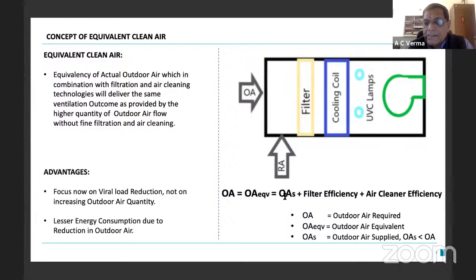This outdoor air equivalent now has three components: the minimum air required, then filter efficiency based on the filtration, and then the air cleaning capacity of the AHU. These three components will now provide the same equivalent of outdoor air which we require in the changed scenario. So this equivalent clean air is the equivalency of actual outdoor air, which in combination with filtration and air cleaning technology will deliver the same ventilation outcome as provided by the higher quantity of outdoor airflow without fine filtration and air cleaning.